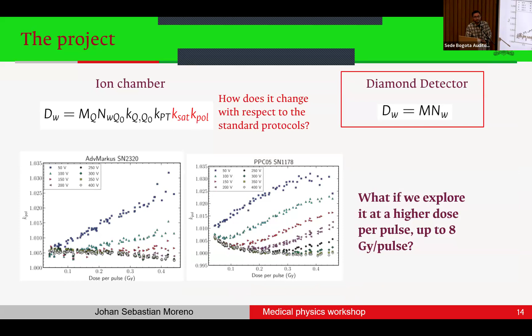This is an illustration of why conventional ionization chambers don't work. In this case, I compared the Markus chamber, and we plot the charge per pulse collected by the ionization chamber as a function of the dose per pulse. As you can see here, the Markus chamber has a saturation, so that's why it's not suitable for this kind of flash beam as we increase the dose per pulse, while the ultra-thin ionization chamber still keeps a linear response.